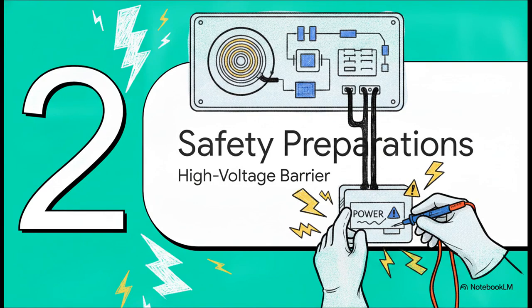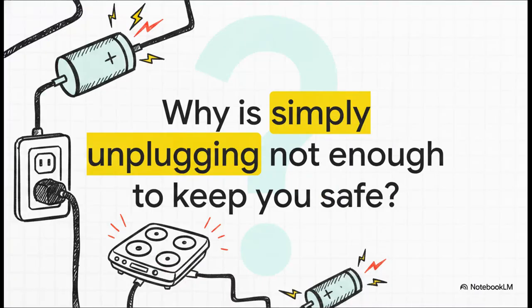Section 2. Critical safety preparations. Crossing the high-voltage barrier. We're shifting gears now. If the outside is fine, we have to go inside. I want to shift the tone here for a second to be pretty serious but empowering. We are about to open an appliance where potentially lethal voltages live, specifically inside that power supply section. Which brings us to a really vital question. Why is simply unplugging the induction cooker not enough to keep you safe? You've cut the power from the wall, so it should be totally dead, right?